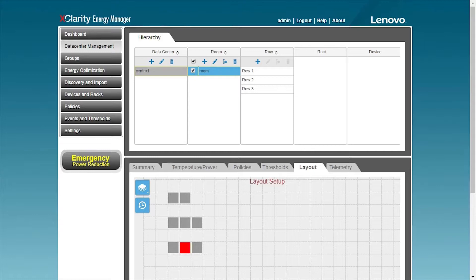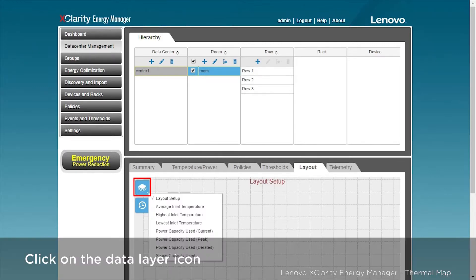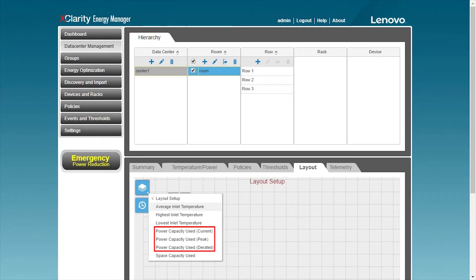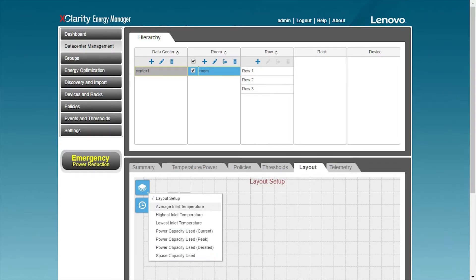In the layout page, you can see that there are 8 racks in the current room, and one rack is colored red, which means that there are servers with temperatures higher than 27 degrees in these racks. After selecting the data layer icon, you can view the rack temperature, power consumption, space capacity, and other information.